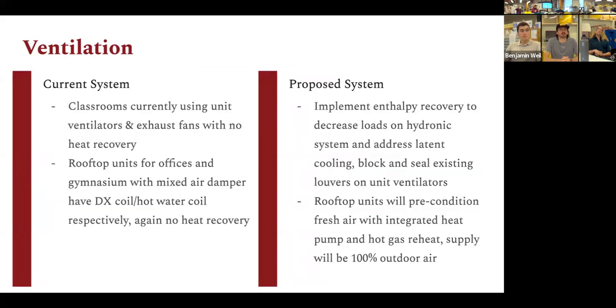For ventilation, the current system, the classrooms currently use unit ventilators and exhaust fans with no heat recovery. And the rooftop units for offices and the gymnasium with mixed air dampers have the direct expansion coil and hot water coil, respectively, again with no heat recovery. So we propose implementing enthalpy recovery to decrease loads in the hydronic system. And the rooftop units will precondition that fresh air with the integrated heat pump, and the supply will be 100% outdoor air.